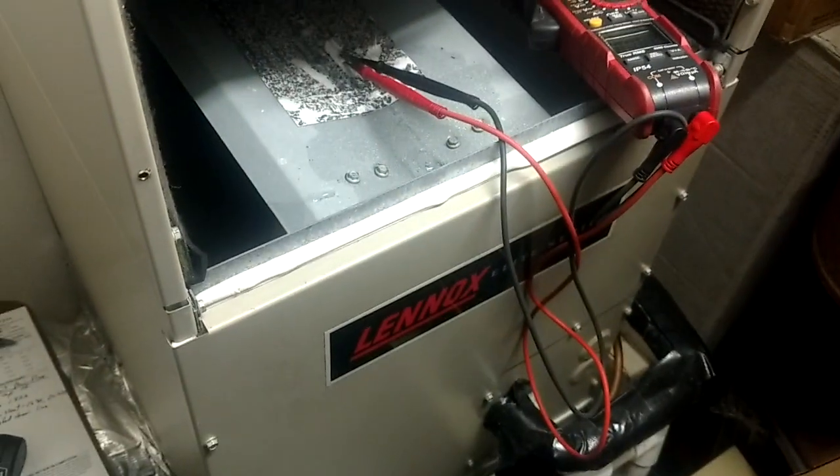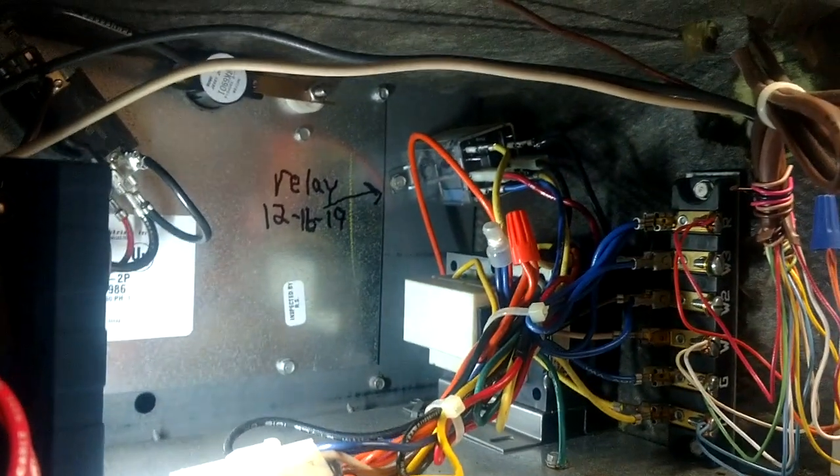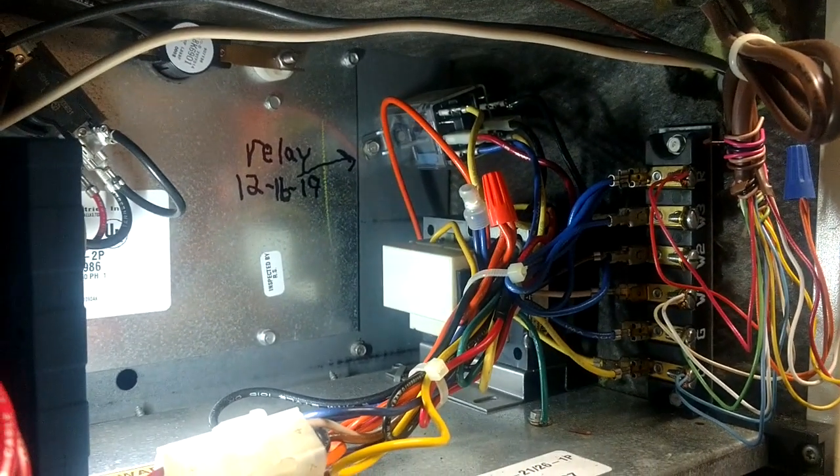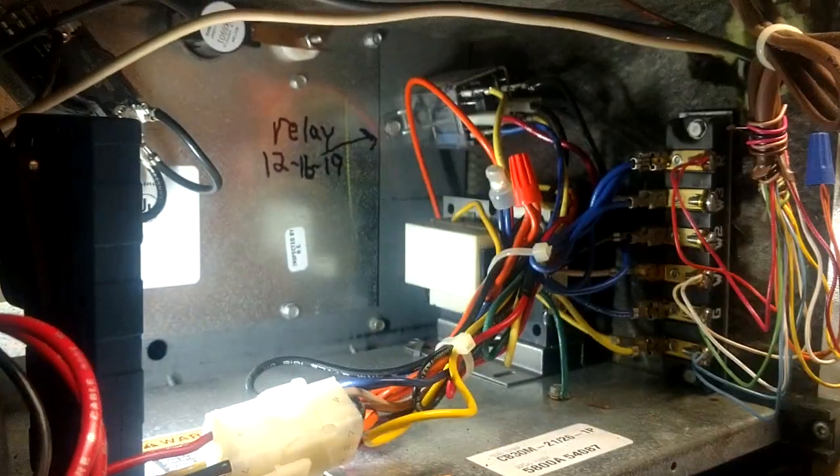Alright, we are here working on the Lennox heat pump - this is an upstairs unit. We've got 5kW of heat and a blower that's not coming on. The homeowner said the fan stopped blowing air out of the vents, and if you see in that back corner we have an ice cube relay.